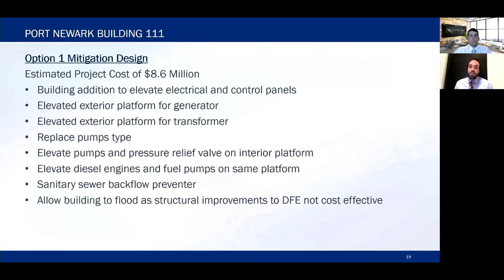We're going to replace the pumps with a horizontal orientation, elevating them on a platform along with the diesel engines that run those fire pumps, and put in a sanitary sewer backflow preventer. We're actually allowing the building to flood, since the structural improvements required to retain 7 feet of floodwater are not cost effective.